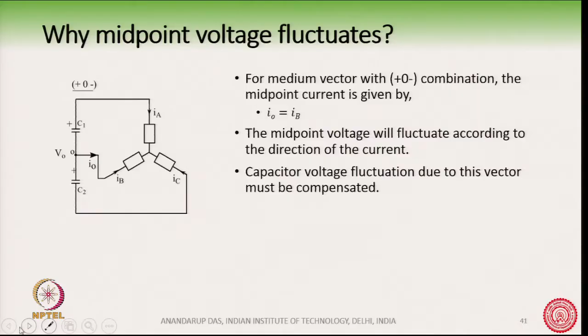Summarizing what happens in sector 1: the 0 vectors will have no effect on the midpoint voltage. The small vectors will have some effect, but the good thing is these small vectors have multiplicities, which we can cleverly use for equal duration to compensate the fluctuation in the midpoint voltage. The problematic one is the medium vector, because it changes the midpoint voltage, but has no multiplicity. So, the midpoint voltage must be compensated by some other means which we will see, and large vectors have no effect on the midpoint voltage.